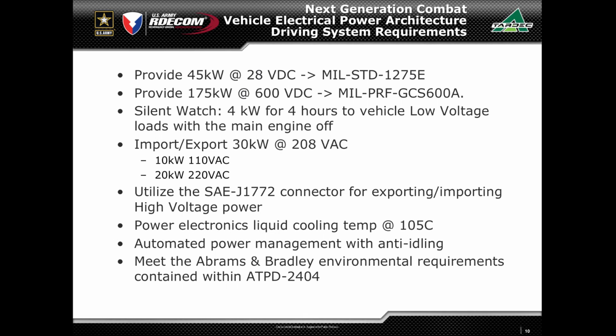Some of those requirements: we have 45 kilowatts of 28-volt power we're looking to produce. The total system power load, on a Bradley-type vehicle, is 175 kilowatts, so that's what we're targeting today for the 600-volt distribution. We're trying to meet our silent watch requirement, engine-off operation of 4 kilowatts for about 4 hours, so we're planning on having low voltage batteries this time, based on where lithium ion is at within the military.